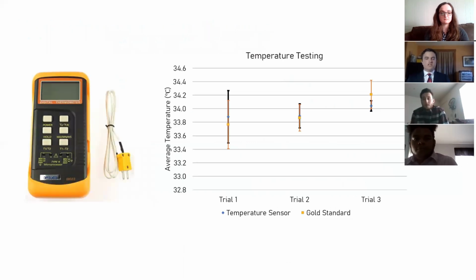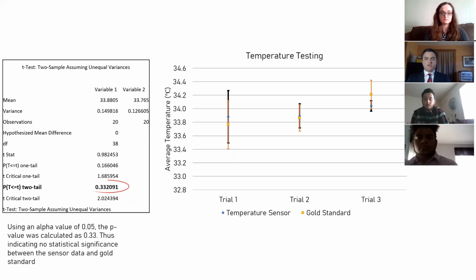Now, in the next slide here, a gold standard 6802 digital thermometer was used. Temperature testing here on the side can be seen for 3 trials conducted on 1-minute intervals for 20 minutes. Now, as you look here, you can see using standard deviation bars as well that there's no difference between the points. They're nearly all identical and overlapping.